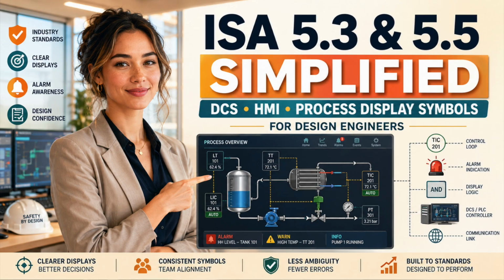A pump symbol should identify a pump, but it should not pretend to tell you everything about the pump. The display must separately communicate whether it is running, stopped, starting, stopping, tripped, unavailable, in local control, in remote control, under maintenance, or suffering from failed feedback. A controller symbol should not merely tell you that control exists. It should clarify whether the function is accessible to the operator, hidden inside the system, executed through a shared controller, supported by an analog backup, or dependent on a supervisory computer.